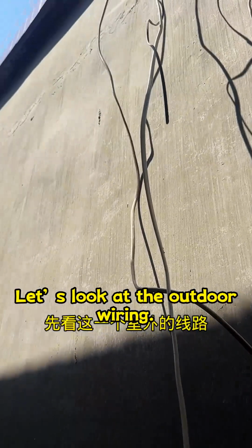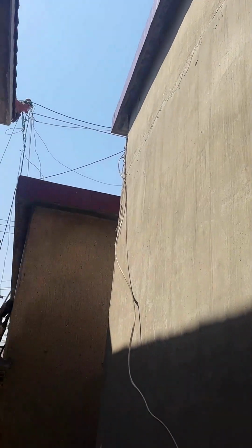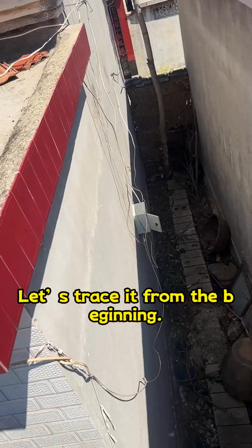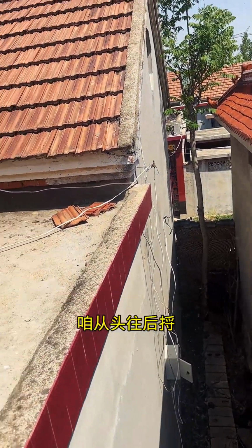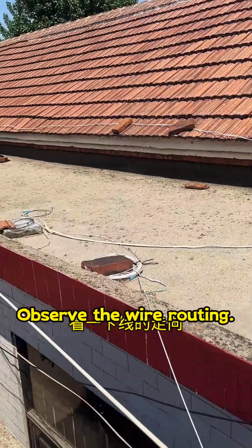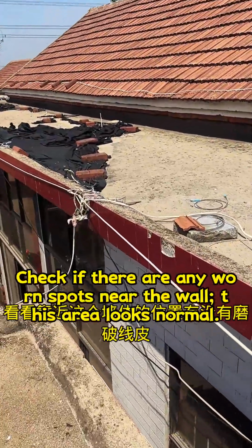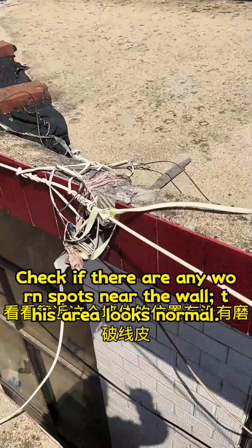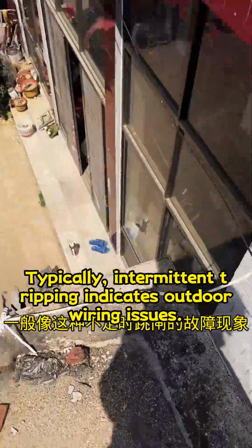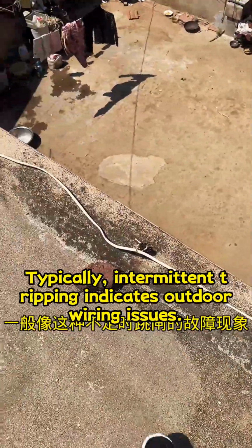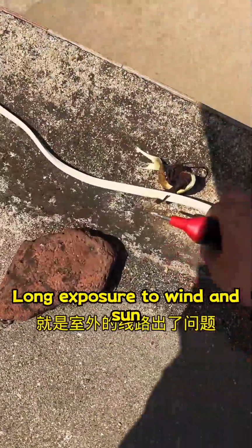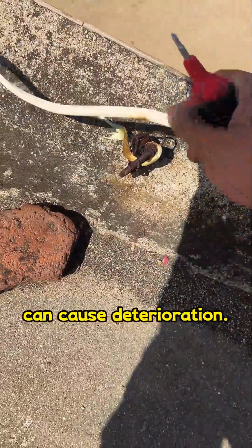Let's look at the outdoor wiring. Let's trace it from the beginning. Observe the wire routing. Check if there are any worn spots near the wall. This area looks normal. Typically, intermittent tripping indicates outdoor wiring issues. Long exposure to wind and sun can cause deterioration.